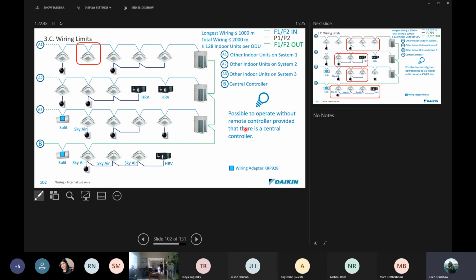Wiring limits. The longest wiring, F1, F2 indoor, is 1,000 meters. The total wiring is less than or equal to 2,000 meters, with less than or equal to 128 indoor units per outdoor system.